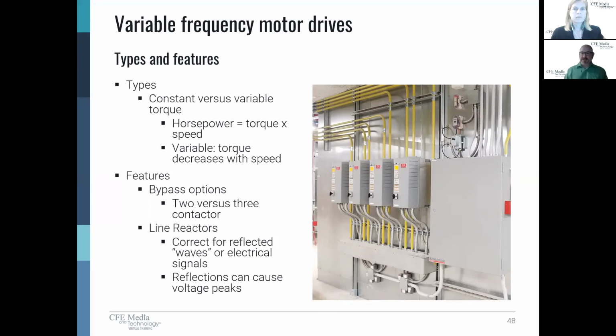But a common way to do that is with VFDs. So variable torque, constant torque, that's a question that a lot of engineers have: which one am I using? So conveyors, for example, are an example of constant torque. That means my torque is high when I'm starting and it's maintained throughout the operational range. A variable torque motor is going to have torque that's fairly low and then it's going to get high as I get going in speed. So from a pump standpoint, a centrifugal pump is going to be variable torque, whereas positive displacement is going to be constant. Go back to our fan discussion. A centrifugal might be variable, whereas a reciprocating compressor might be constant.